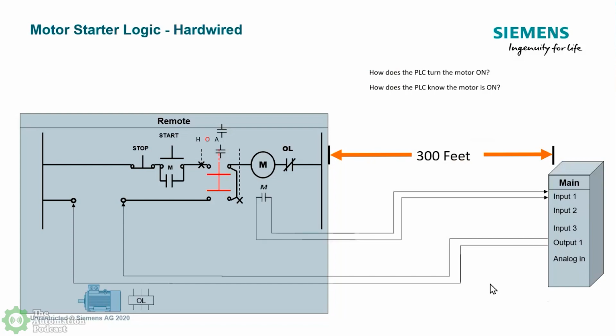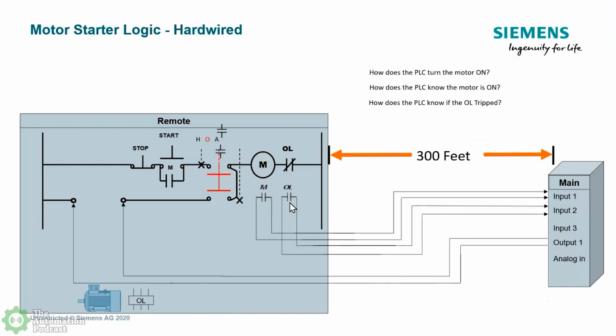So if we continue with that little bit of laying out the logic and the hardwiring, if we build a little bill of material, you have the opportunity to bring in the closing. You've got the sealing circuit here, which is an additional contact that needs to be wired in. And then again, when I think of a contact, that can be a trouble point for troubleshooting, to verify that if this contactor has failed, then the motor, when they push start, won't stay maintained and run. So there's the troubleshooting point. And then there's an overload, of course, another contactor that comes in. And bear in mind, we've got analog input cards, digital ins, digital outs that you have to tie for one motor.